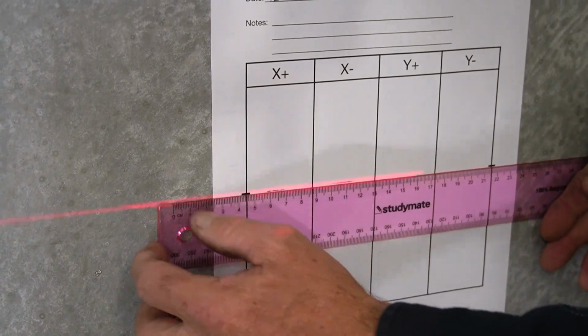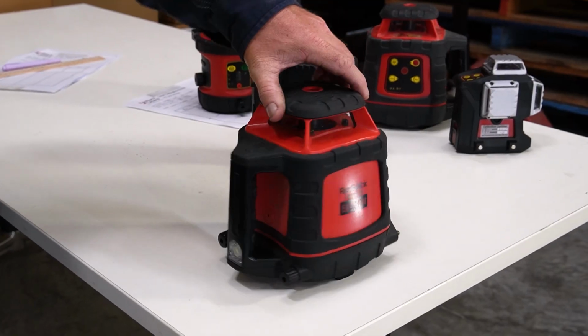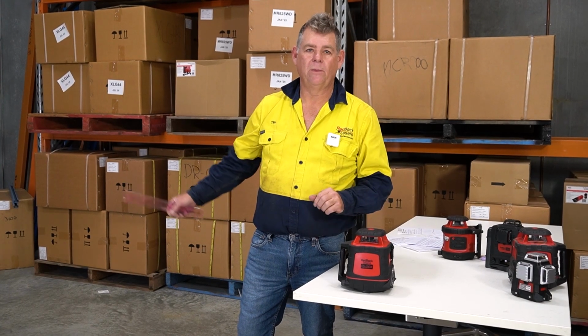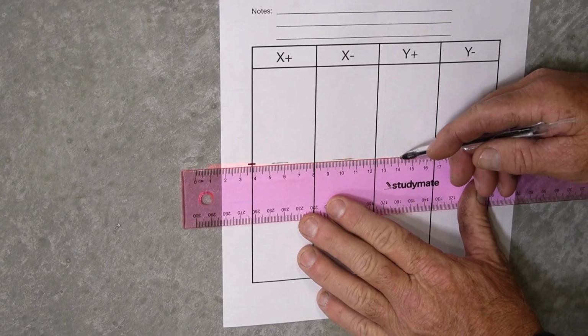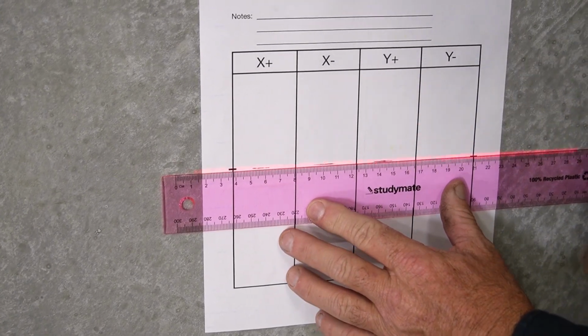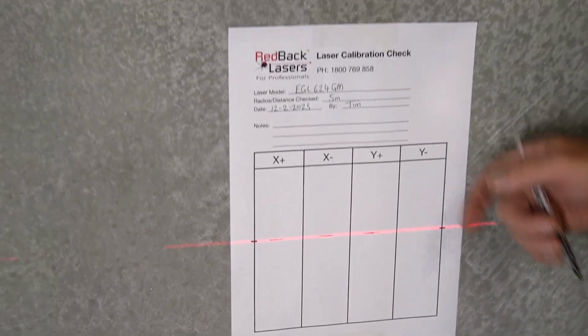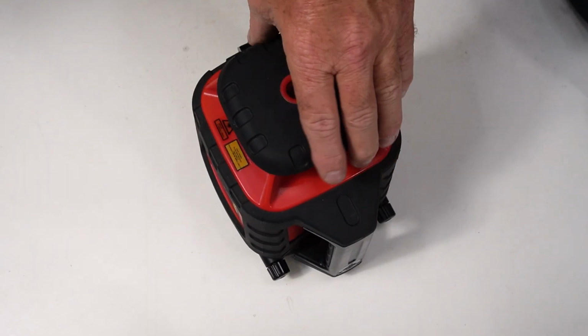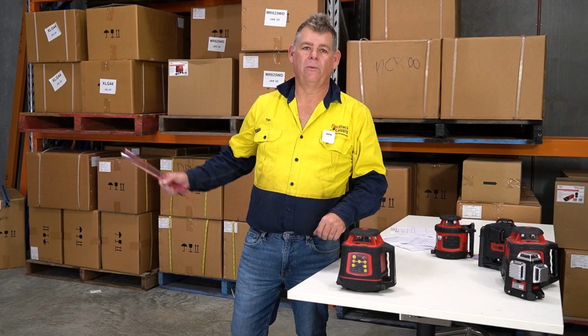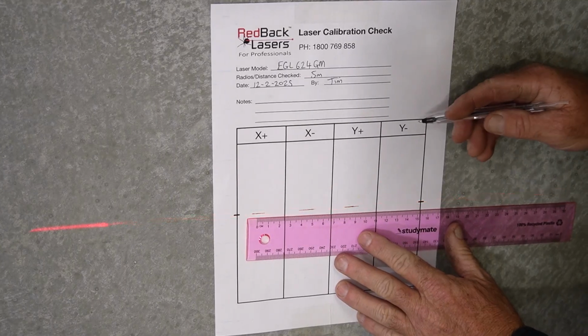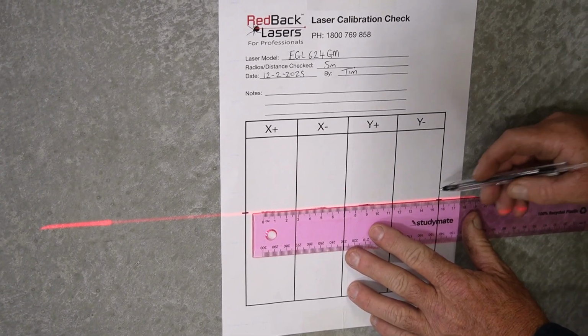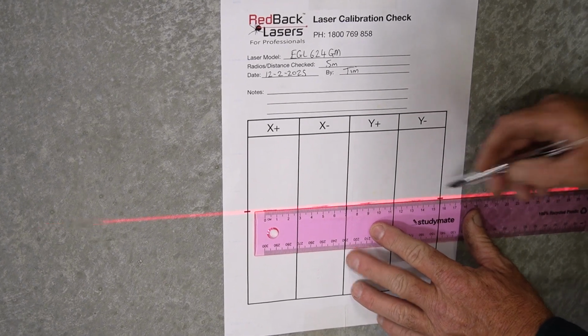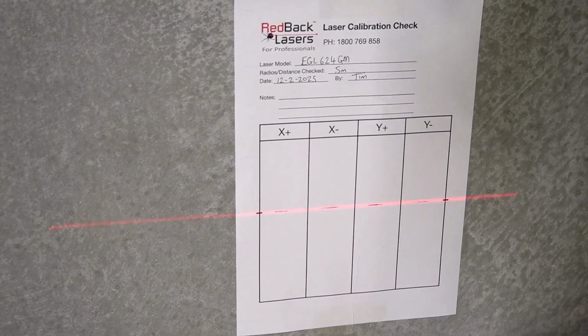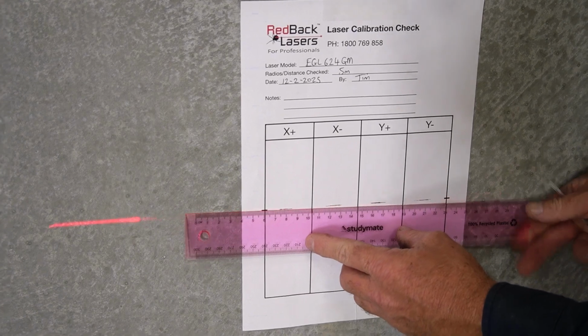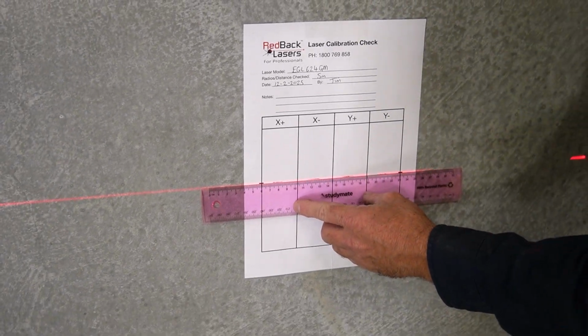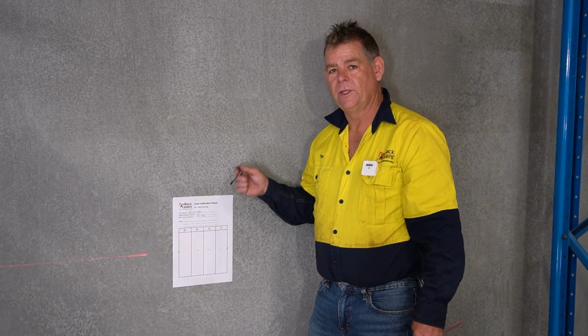Then we rotate that laser 90 degrees, so the Y arrow is aiming at our calibration check sheet. Do another 10 millimetre line, and now we've got the Y positive axis. Rotating the laser 180 degrees on the Y axis, so we can pick up the Y minus. So now we've got the Y negative aiming at the calibration check sheet. We do our last marking across there, and as we can see, we've now drawn a straight line across our calibration check sheet. So we know our laser's within calibration.